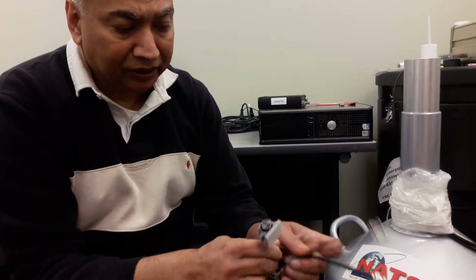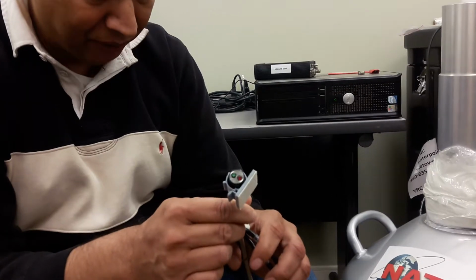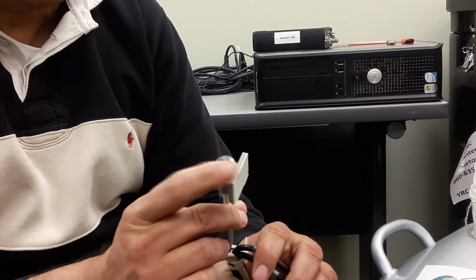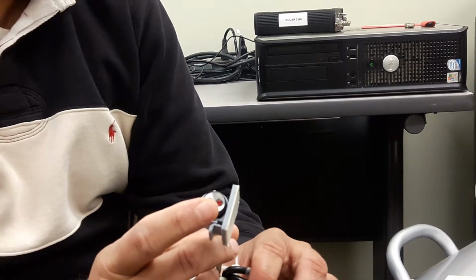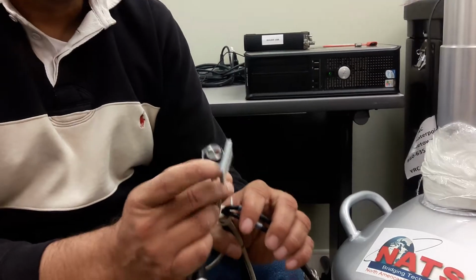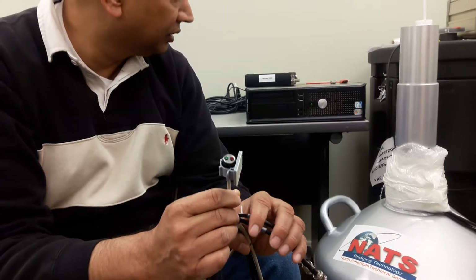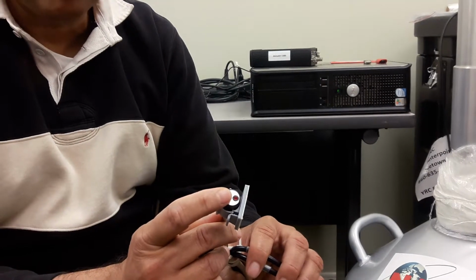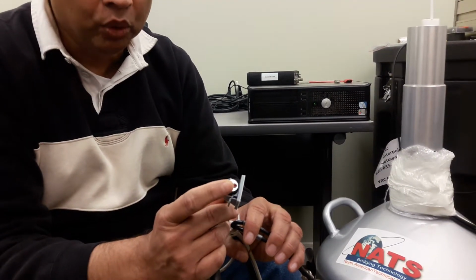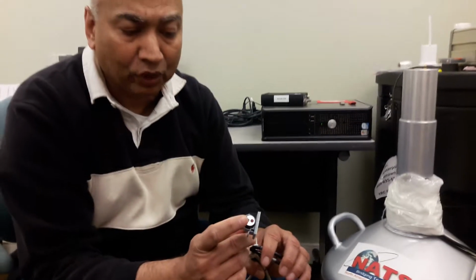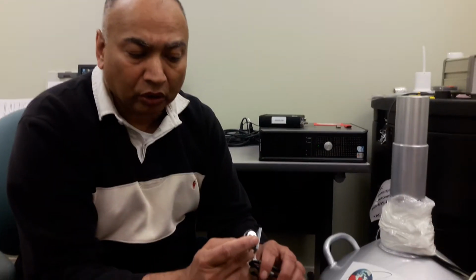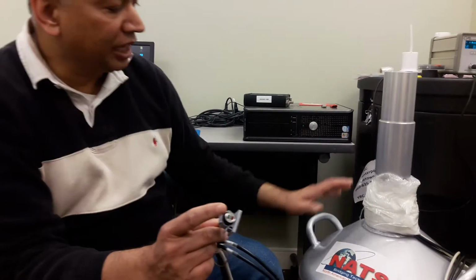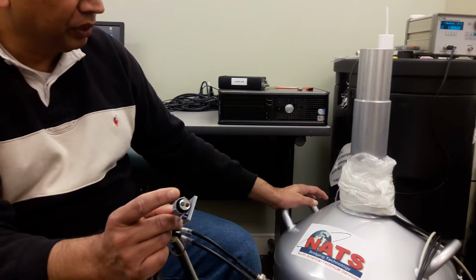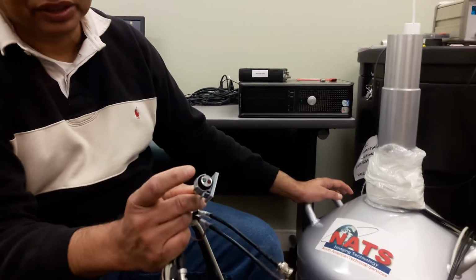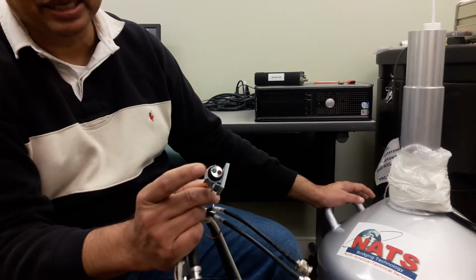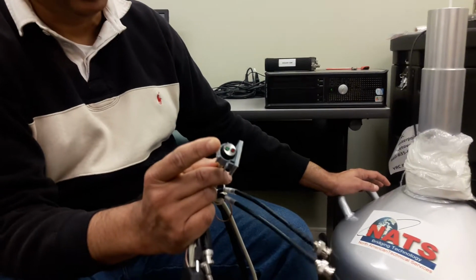Depending on the type of detector, this type of detector will also have a high voltage LED and inhibit line signal. There is a green and a red LED, and we will see during the operation of the unit that once you specify the type of inhibit circuit that is in the system, this light might go on, showing you whether the detector is adequately cooled. If it's cool, as soon as you try to apply high voltage, it will show a green light, and if it is not cool, then it will show a red light. If your detector has been cooled for more than 24 hours in liquid nitrogen, then when you connect it and have the right circuit, it will show you a green light here, which is going to show you the detector is cooled.